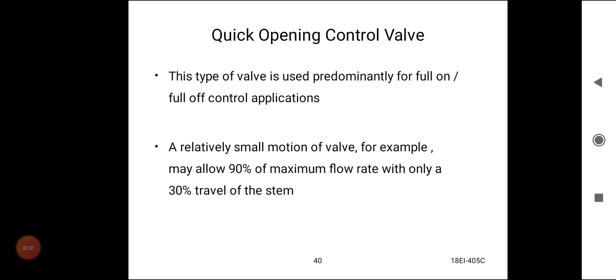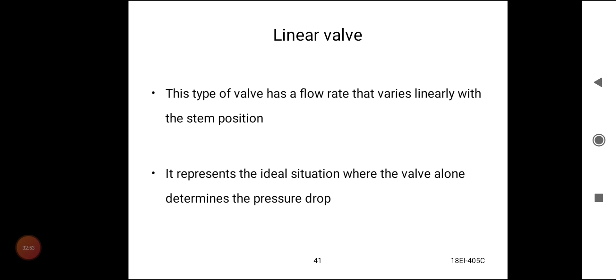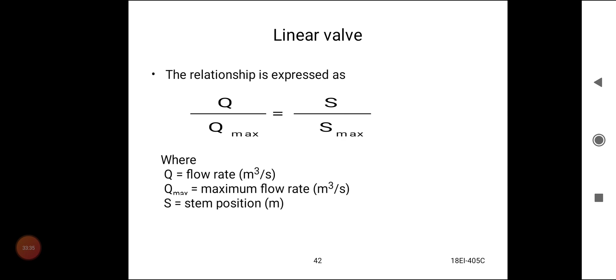Linear valve. This type of valve has a flow rate that varies linearly with the stem position. It represents an ideal situation where the valve alone determines the pressure drop. The relationship is expressed as Q by Q maximum equivalent to S by S maximum, the ratio between the quantity rate of flow and the maximum rate of flow equals the ratio between the stem position and the maximum allowable stem position, where Q is flow rate in meter cube per second, Q maximum is maximum flow rate in meter cube per second, S is stem position in meters, S maximum is maximum stem position in meters.